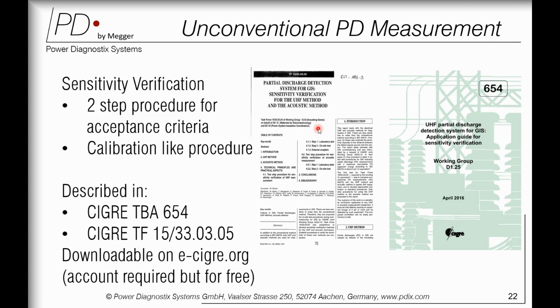You might have a question: how do we know that the number of UHF sensors installed in the GIS is more than sufficient? That means, what is the calculation, how do the GIS OEMs calculate how many sensors need to be placed? There is one document, CIGRE TB 654, which gives you the method to make sure that the number of sensors provided by the OEM is more than sufficient, so that there is no blind spot left in the GIS. It might be possible that someone has reduced the sensors to reduce the price, which directly affects your sensitivity when you do the PD measurement in your GIS. This is also known as the sensitivity verification test. As per CIGRE, it is a two-step procedure which looks like a calibration, but it's not a calibration.